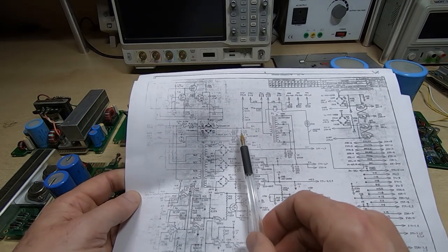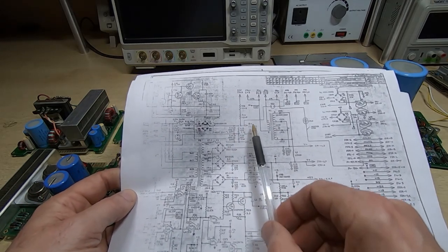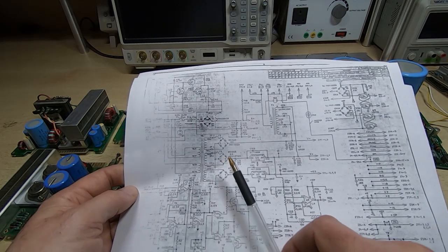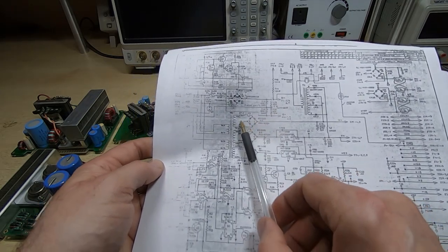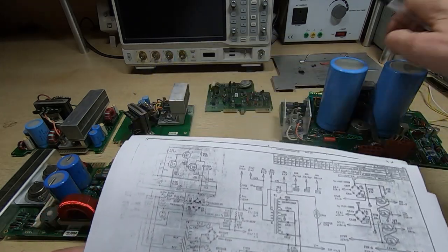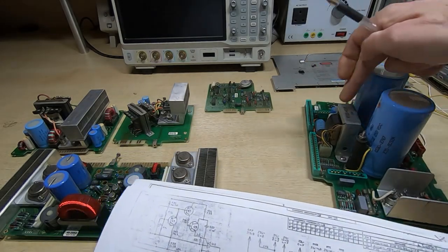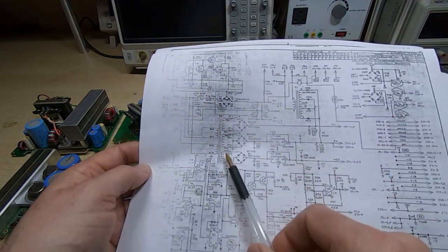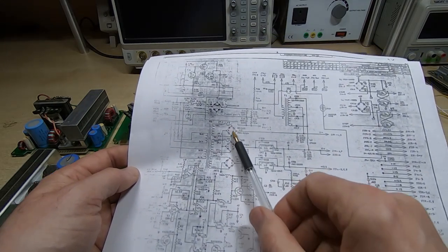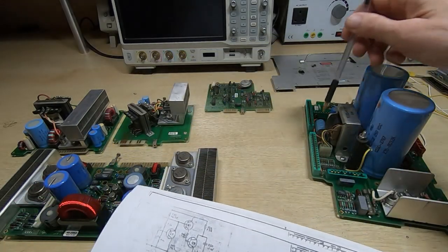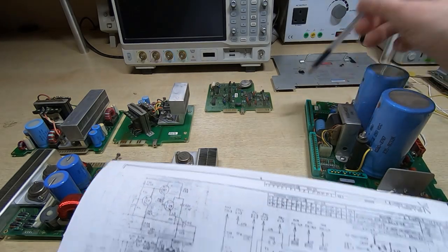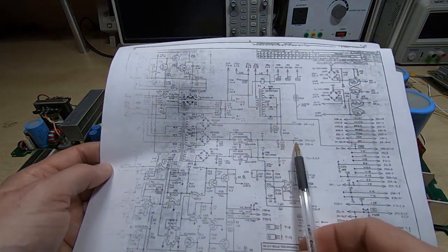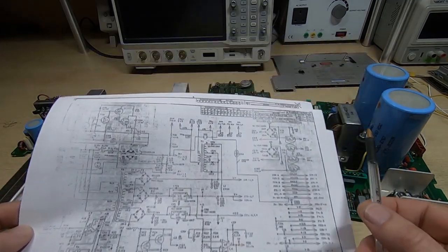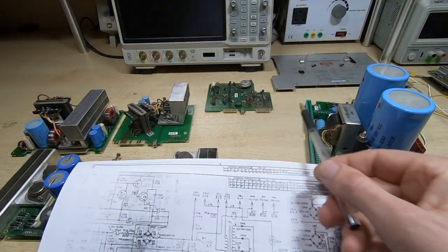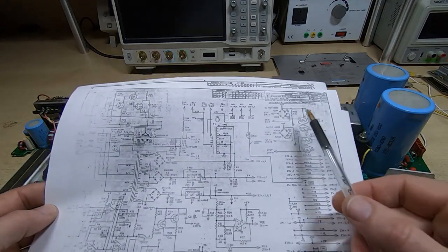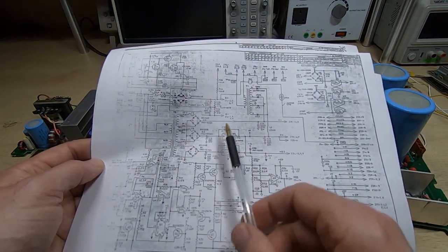So we have the plus or minus 160 volt DC rail, and we also have this secondary supply down here, formed using this transformer. It just feeds into a few bridge rectifiers, the small ones you probably can't see, down here. These supplies are used internally for the circuits of the power supply itself - they don't supply power to the actual machine, just to power the power supply.